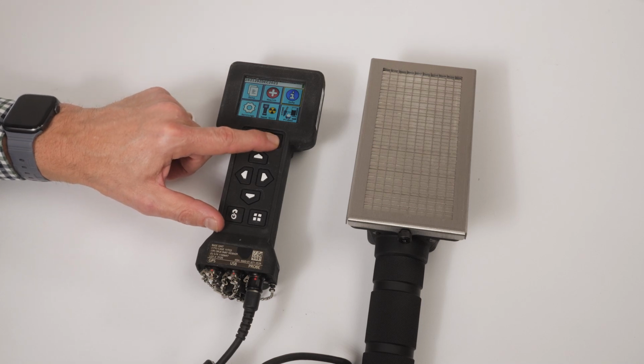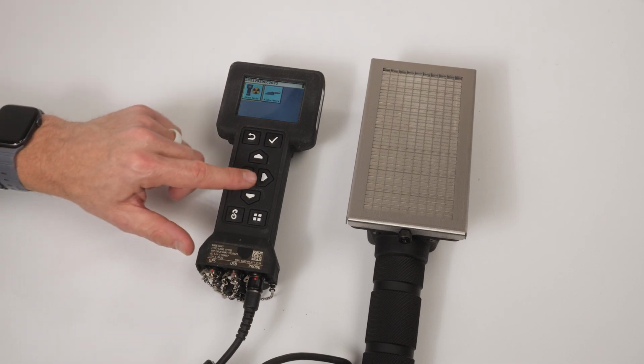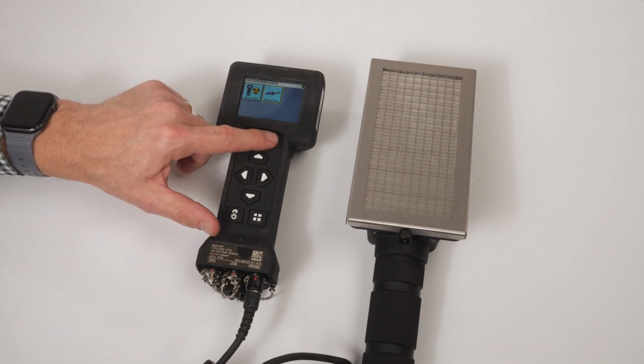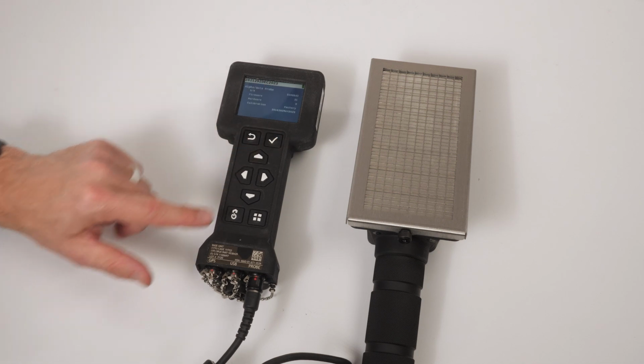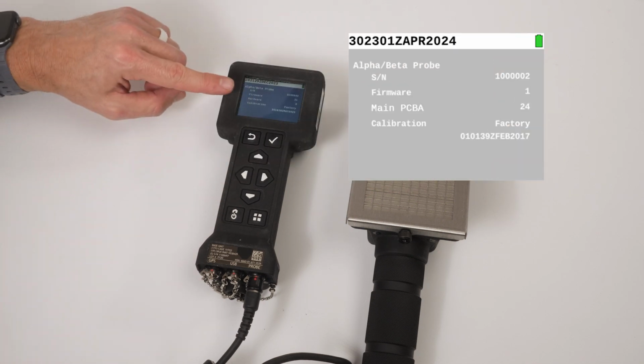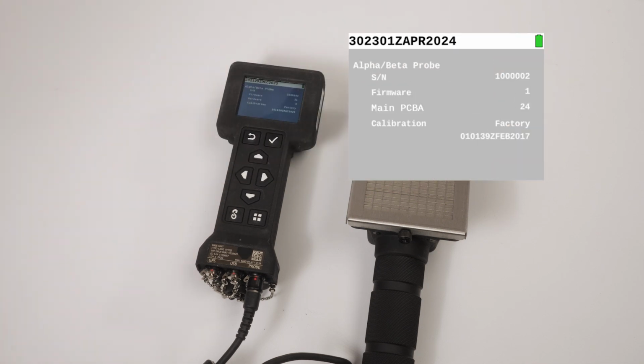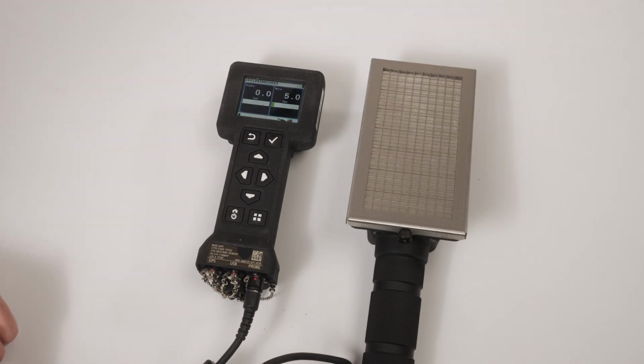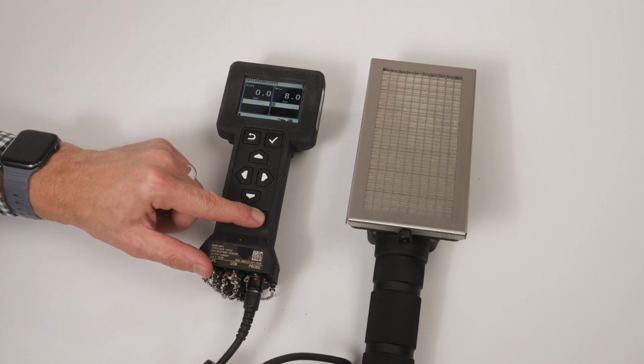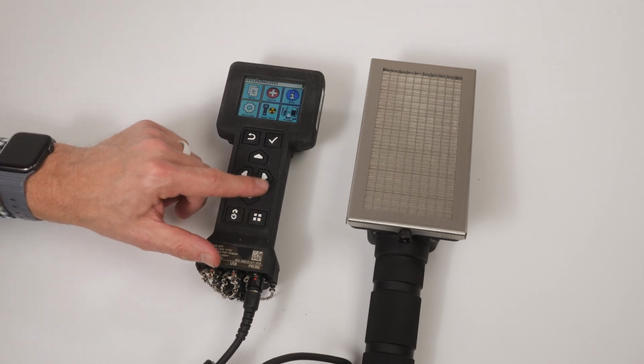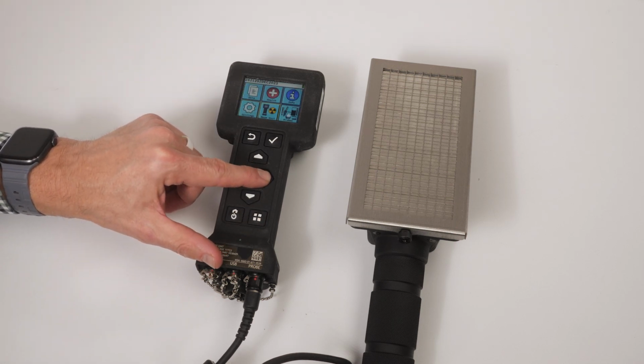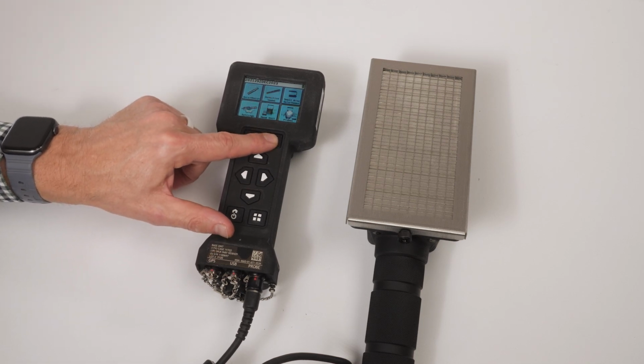Use the arrow keys to highlight the alpha-beta icon and press the enter key to select. From the info menu, you can view the serial number of the probe, firmware version, printed circuit board version, and calibration information. To change the radiation measurement units for the alpha-beta probe, press the menu key. Use the arrow keys to highlight probes, then press enter.